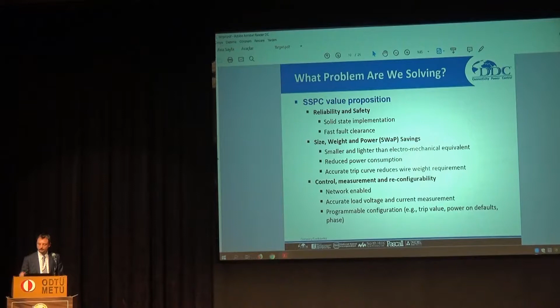If you're using a standard mechanical breaker, you have to choose the current rating before you design your system. With one of these SSPC cards, basically, you can program it by software. These channels have fixed current ratings, which you can adjust by software according to the loads behind it that need to be protected. For example, a 25 amp channel can be programmed down to 2.5 amp, so you can adjust the channel afterwards to the needs of your system. And this also gets the system, let's say, ready for the future. If you connect a new load to the solid-state power controller, you have the ability to program the current limit of that single channel, again by software.